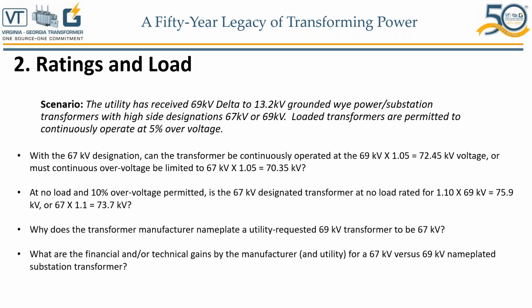But coming back to 5% over voltage, the answer is yes. What I cannot answer correctly here, because I do not understand what it means to have a transformer 67 or 69, but yes, you can operate your transformer at 1.05 pu no load voltage. Is it recommended? Maybe, maybe not, depends on who you buy your transformer from, but yes, per the standards, we have to design and build them to continuously run all the way up to 110%.